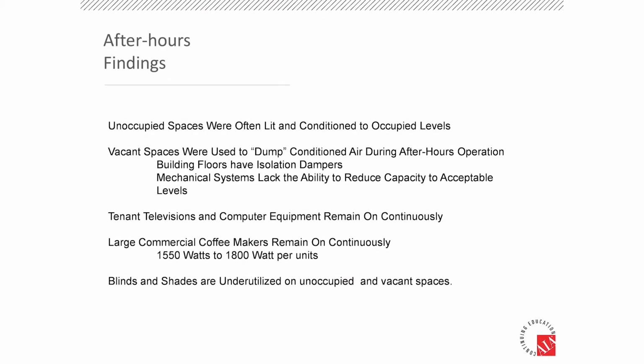Additionally, to go back to the Energy Star benchmarking, we're looking for any large energy consumers. With a low score, they're using a lot of energy. What is it? Is there anything obvious? So here's what we found when we looked at the after-hours operation of the building. We saw often that unoccupied spaces were lit and they were conditioned to occupied levels. Vacant spaces, and by vacant spaces, I mean spaces which have been demoed and are completely open, no tenants, were used as a space to dump air during after-hours operation.